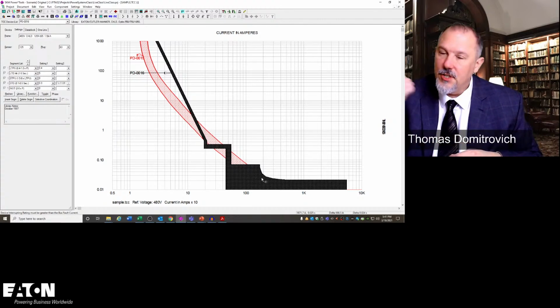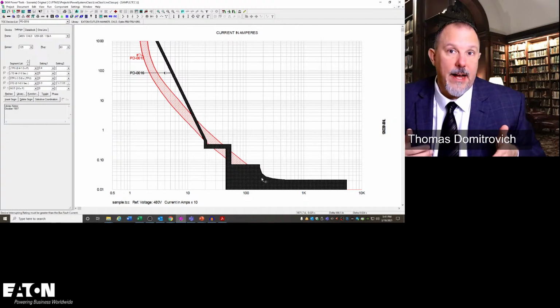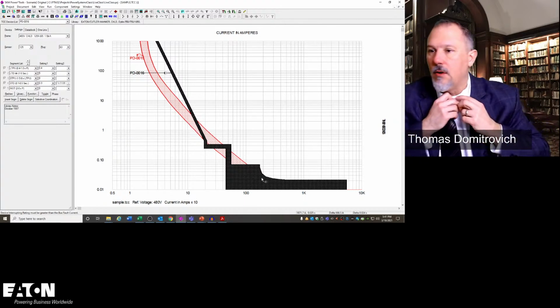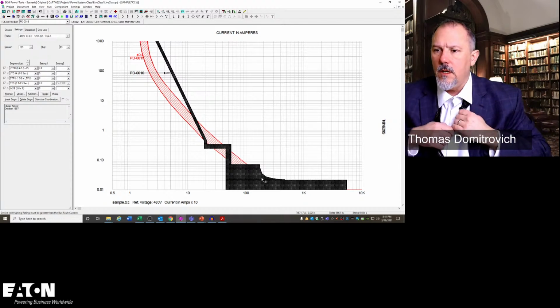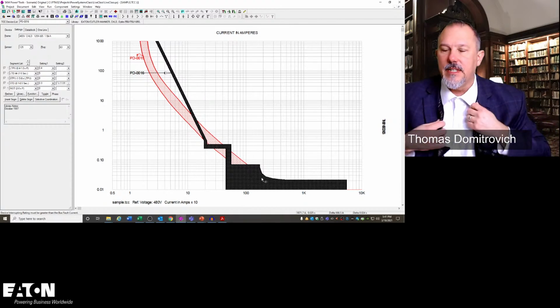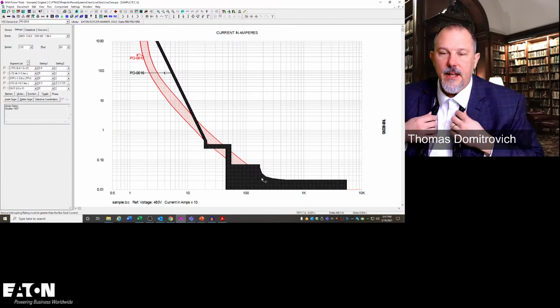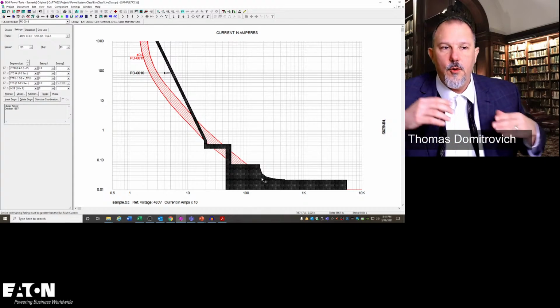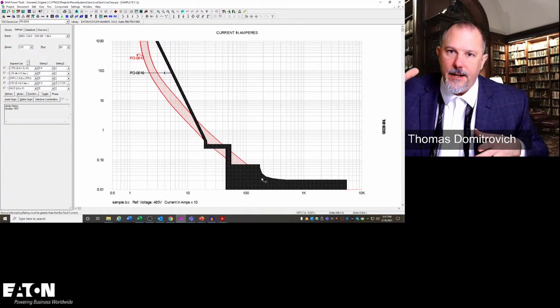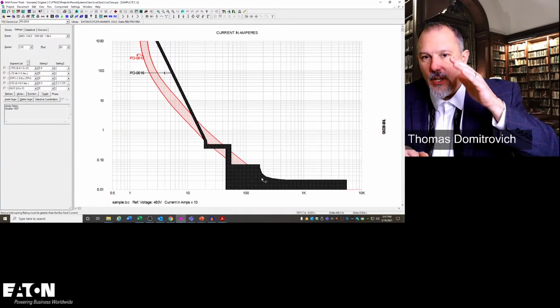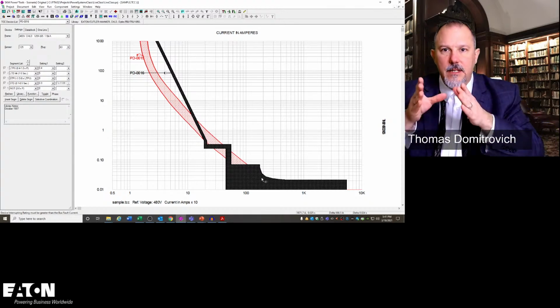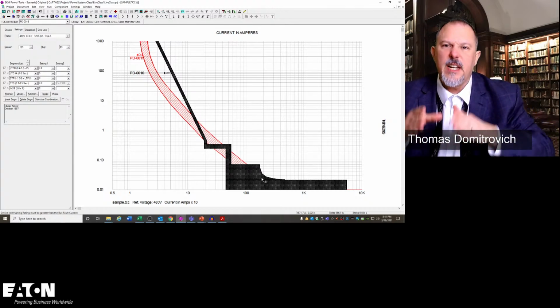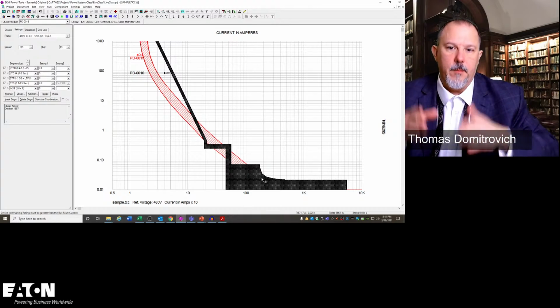Or I was just talking to a gentleman who's working on a 400 hertz system. If you're at 400 hertz, your trip curve is going to change based upon the frequency that you're at. And where do you see 400 hertz? We see 400 hertz in minus 20 to 30% tolerance in the instantaneous region. There you go, MC. Thank you. So you'll see 400 hertz like in airplanes and stuff like that. But you've got to understand that there's bands, and you've got to read the TCC curves. The TCC curves have a lot of very important information.